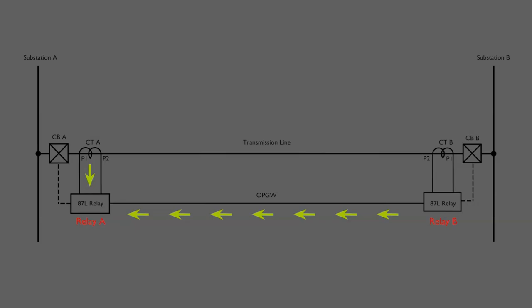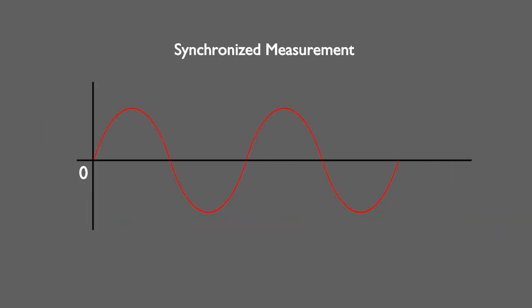To overcome this, differential relays adopt methods to ensure accuracy — the relays use synchronized measurement. Suppose the red sinusoidal wave represents the replica of the primary current of CTA. If we draw the green sinusoidal wave of CTB at relay A, it will be in negative. The green sinusoidal wave represents the replica of the primary current of CTB at relay A. You see there is a time delay of the green wave with respect to the red wave, due to the propagation time of the green wave from relay B to relay A. If both currents are the same but there is still a comparison error, this may cause a malfunction of relay A and trip the associated circuit breaker unnecessarily. This difficulty is eliminated by using synchronized measurements.